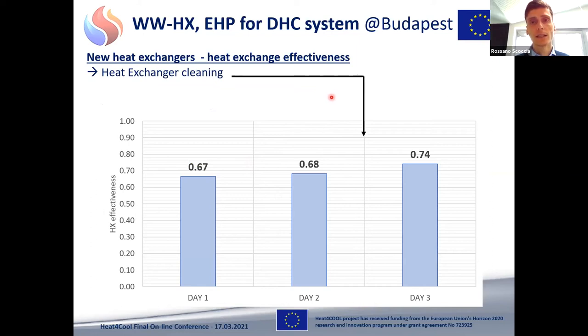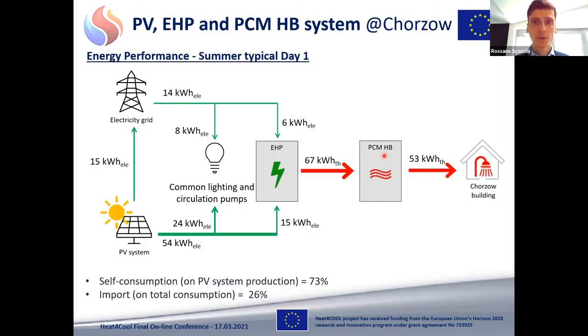Then the last slide on Budapest shows you the effectiveness of the new heat exchanger cleaning method that was implemented. And here you see how the heat exchange effectiveness increased from 68% to 74% after the cleaning of the heat exchanger. Now we move to the last case, the last package, the one composed by PV, electric heat pump and phase change material heat batteries. Here I show you the results for Chorzów case study.